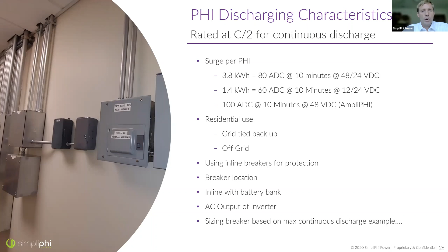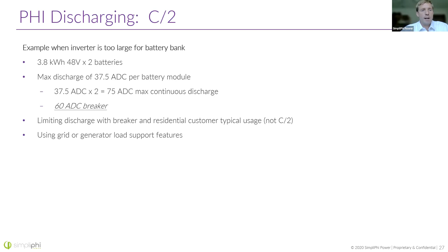Again, on the discharging, just going over this, I think we've kind of covered this, but the rate is per battery, right? And this is an example where we're going to do a calculation, an example when an inverter is too large for a battery bank. If you have 2 3.8 kilowatt hour 48 volt batteries, the max discharge rate you can have there is 37.5 amps per battery module. You got 2 of those, that gives you 75 amps. 75 amps at 48 volts, right, is the amount of power you could draw out of your battery bank. If we put in a 60 amp DC breaker, that should prevent the battery bank from discharging faster than 75 amps. I'll get into a little bit about how breakers work here and how slow they can be to respond in a second. So let's talk about that.